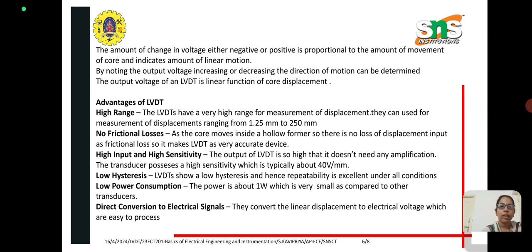The advantages of LVDT: first, it is of high range. LVDT has a very high range of measurement of displacement. They can be used for measurement of displacement ranging from 1.25 millimeter to 250 millimeter. There are no frictional losses as the core moves inside the hollow former, so there is no loss of displacement input as friction losses, which makes LVDT a very accurate device. Third is high input and high sensitivity. The output of LVDT is so high that it does not need any amplification at all. The transducer produces a high sensitivity, typically about 40 volt per millimeter.